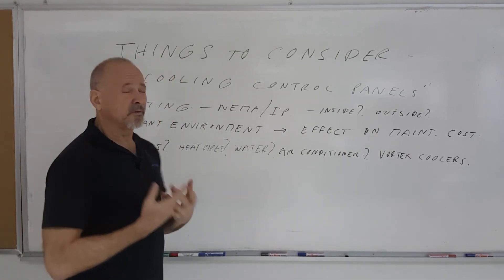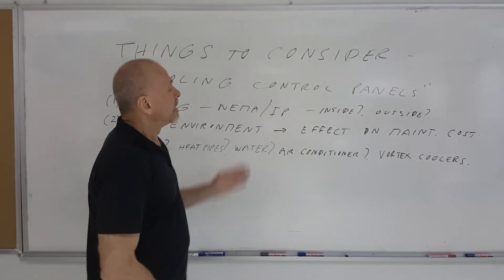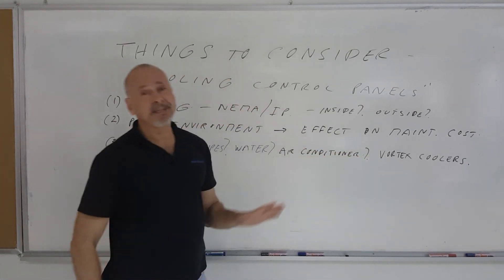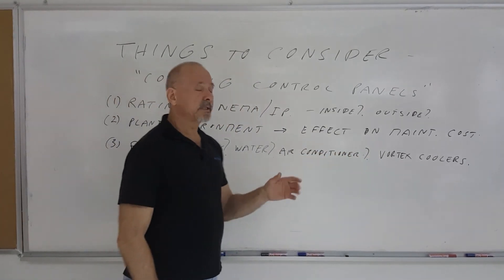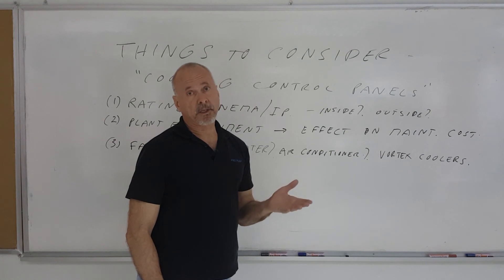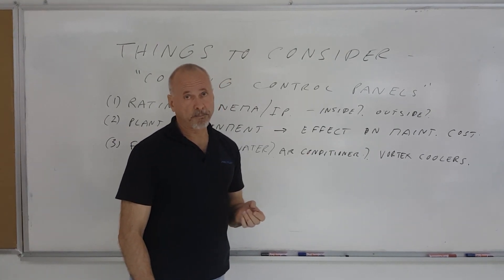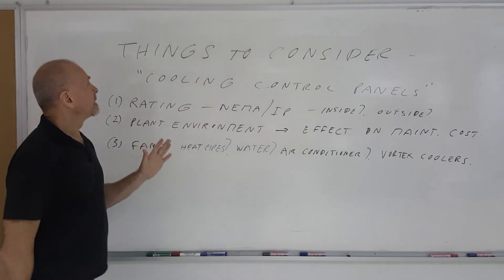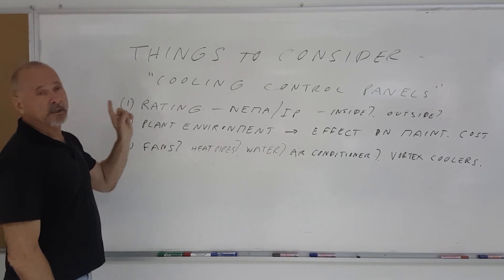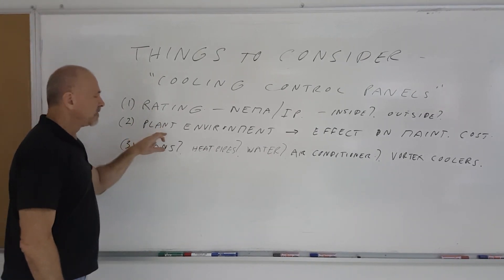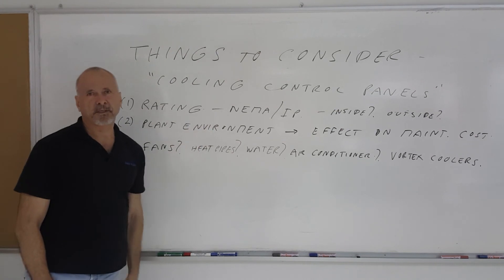So when you get to a very dirty environment, that's when you start looking at vortex coolers because the maintenance savings offset any increased energy cost utilizing the compressed air. So these are the things to consider in cooling a control panel. The rating of the panel, the factory environment, and then of course you have these choices to make.